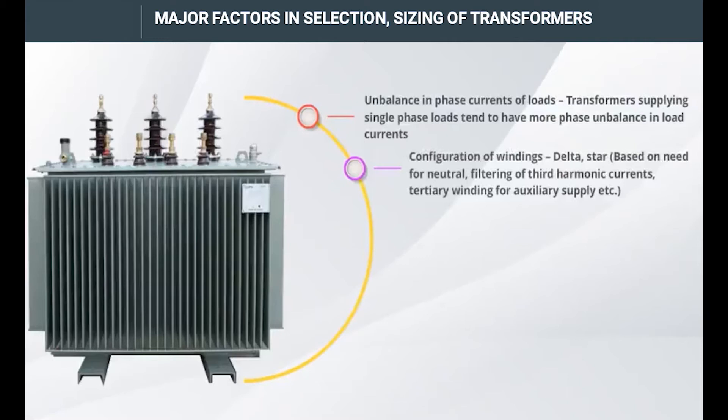Configuration of windings — whether delta or star — needs to be determined. This is based on the need for neutral, filtering of third harmonic currents, a tertiary winding for auxiliary supply, and other requirements.